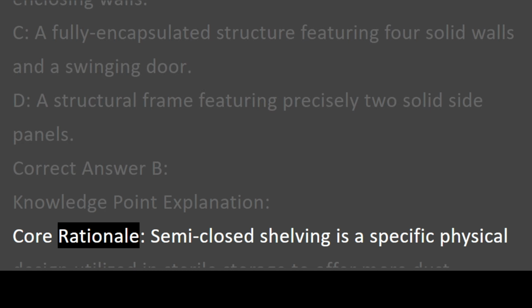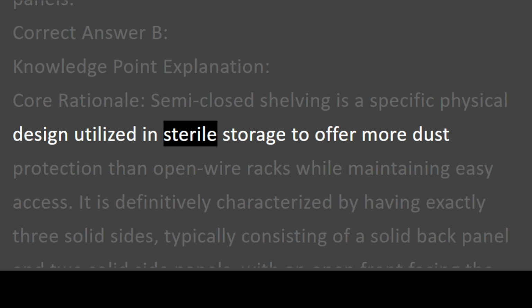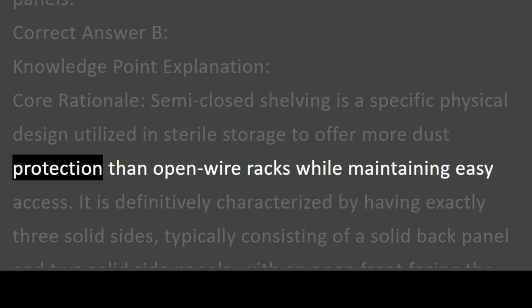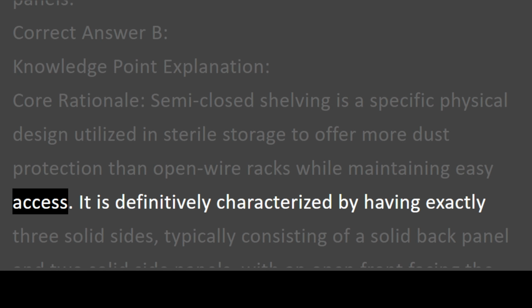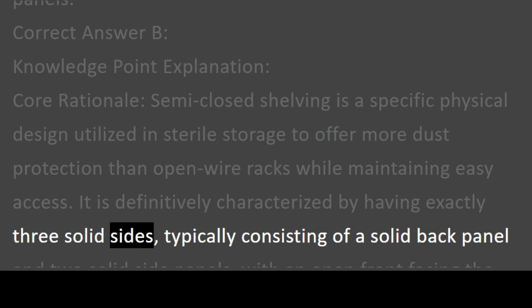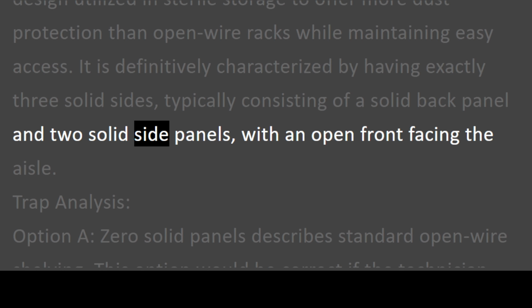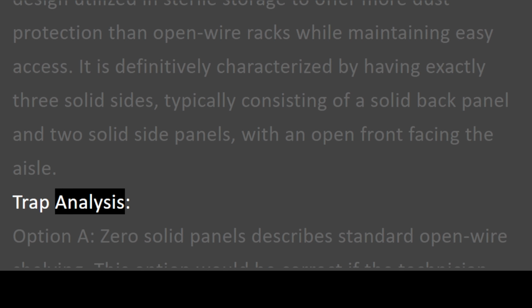Core rationale. Semi-closed shelving is a specific physical design utilized in sterile storage to offer more dust protection than open wire racks while maintaining easy access. It is definitively characterized by having exactly 3 solid sides, typically consisting of a solid back panel and 2 solid side panels, with an open front facing the aisle. Trap analysis. Option A. 0 solid panels describes standard open wire shelving.